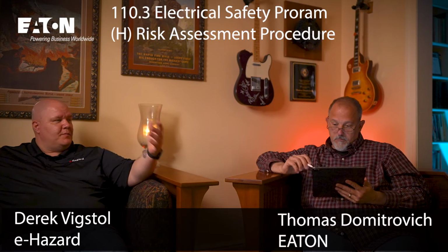Yeah. And here's the other piece that gets missed in a shock risk assessment. We tend to say all the time that as qualified people, we can be inside the limited approach boundary, correct? Yes. Do we add on to that with justification? Can I pull up and eat my lunch inside? No. That's right, you have to have a reason to be there. So what's my reason? I can go into that limited approach boundary and take that panel board cover off because you need it off for your thermography. And I can take it off while the equipment's still energized because you need the equipment at operating temperature, so an interruption in service would screw up the readings. That's right, it's infeasibility. That's exactly right.